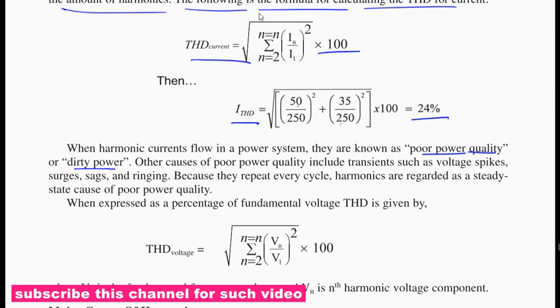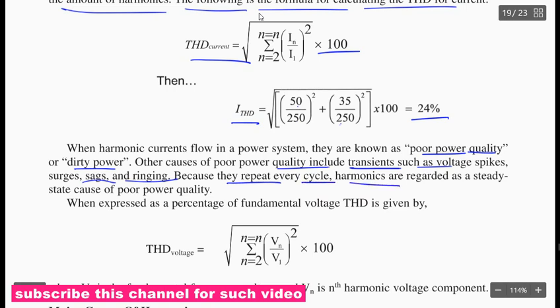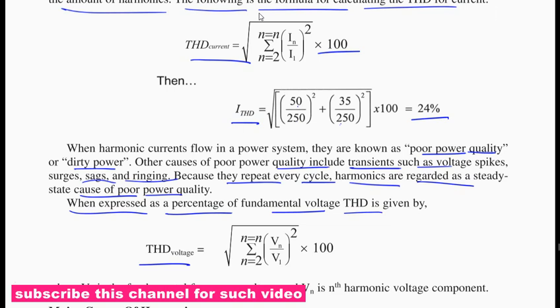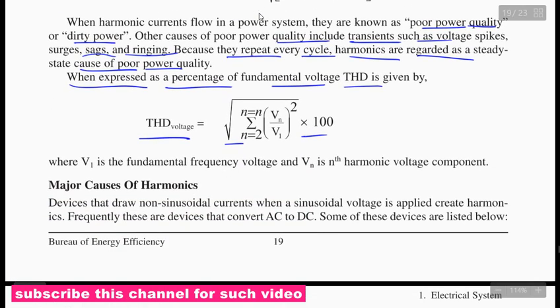Other issues of poor power quality include transients such as voltage spikes, surge, sag and ringing. Because harmonics repeat every cycle, they are regarded as steady state poor power quality. When expressed as a percentage of fundamental voltage, total harmonic distortion is given by the square root of the sum of Vn squared divided by V1 squared, into 100, where V1 is the fundamental frequency voltage and Vn is the nth harmonic voltage component. Major causes of harmonics.